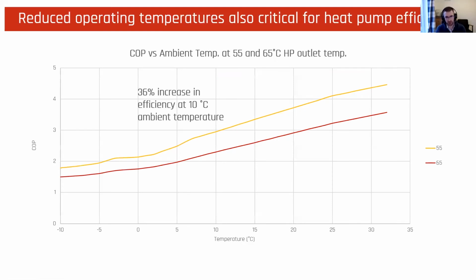Tom put this up earlier, so I'm not going to go over it too much, but as well as heat losses, this distribution temperature is all about, particularly for air source, improving the efficiency of the overall system by not asking it to operate at an extremely high temperature. And this again is the Mitsubishi chart, but just taking an annual average temperature that we would typically see at 10 degrees, the difference between operating the system at 55 as opposed to 65 is a 36% increase in efficiency at that ambient temperature. So there are massive gains to be had by getting the distribution system temperatures as low as possible. And that really starts at stage 1, stage 2 design.